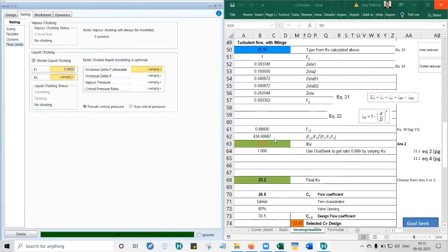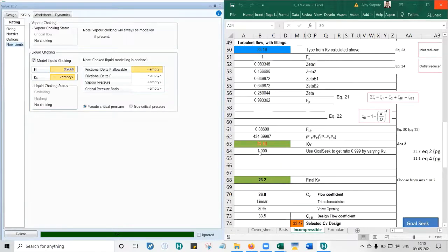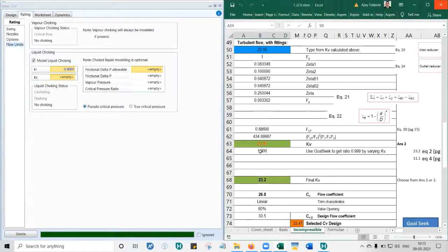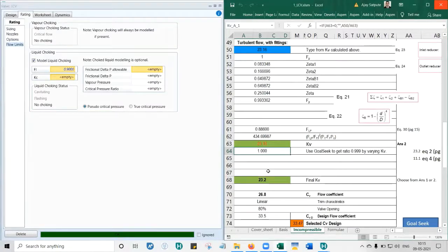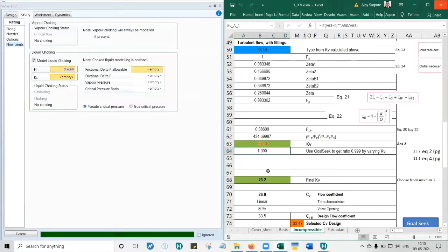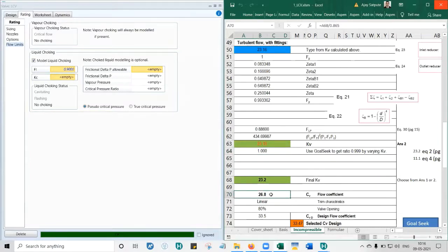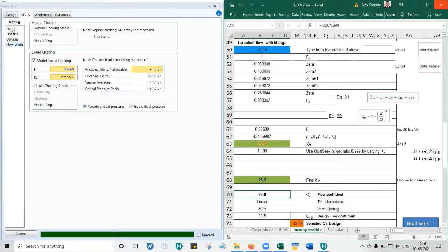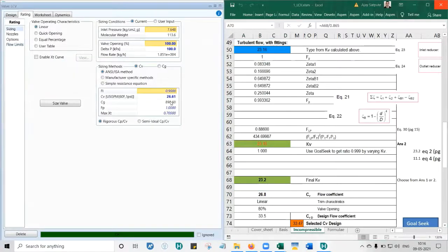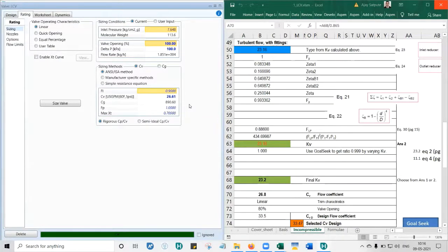Scroll down. If it is in A64 cell, the ratio should be 1. If you remember control valve, the ratio should be 1 and we get it 1 value by using Goal Seek. By changing A50 cell to 23.16, final KV will be 23.2 and final CV would be 26.8 - because 23.2 divided by 0.865 is the conversion from KV to CV. Let's check with HYSYS value. What are you getting? 26.6, 26.8. So we can trust HYSYS.